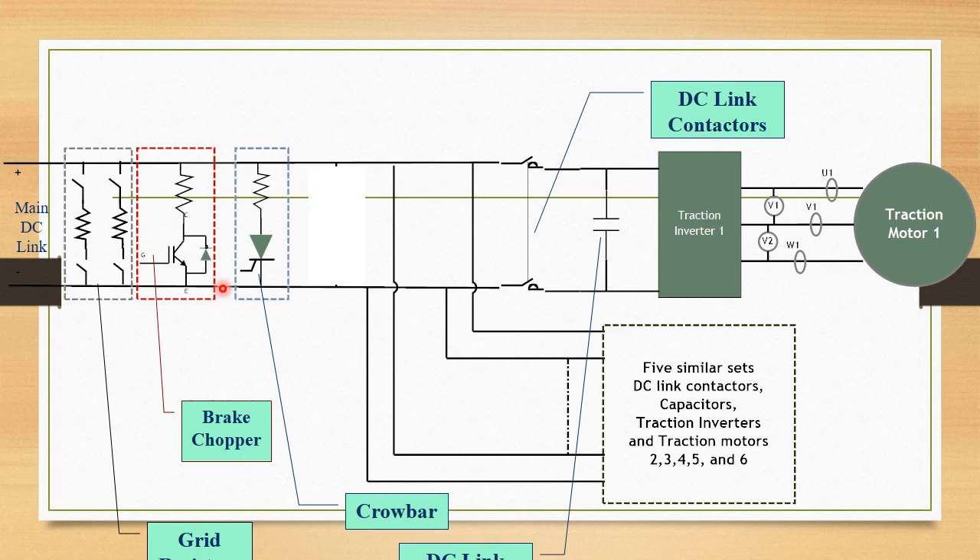After this, if the voltage is yet high — more than 2800V — then a secondary safety device called the crowbar comes into picture. This crowbar fires in two ways: one is soft crowbar firing and one is hard crowbar firing. The resistance used is 2.94 Ohm, with two resistances in parallel giving a resultant resistance of 1.47 Ohms.